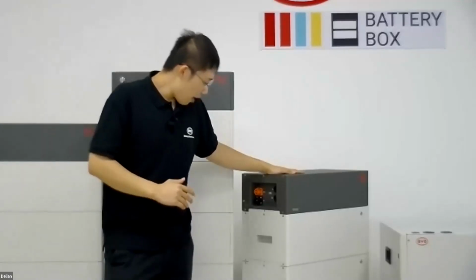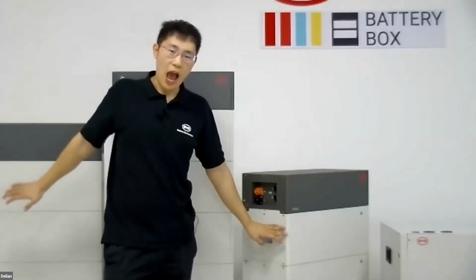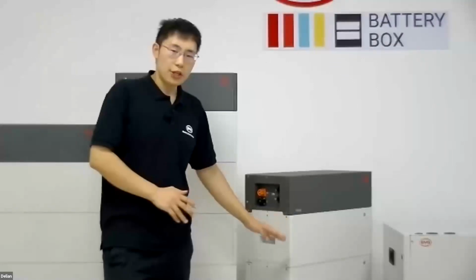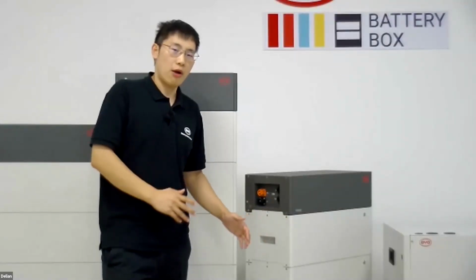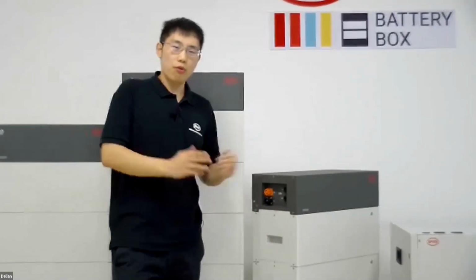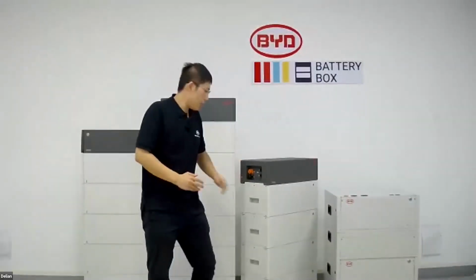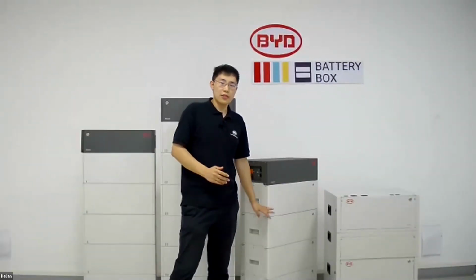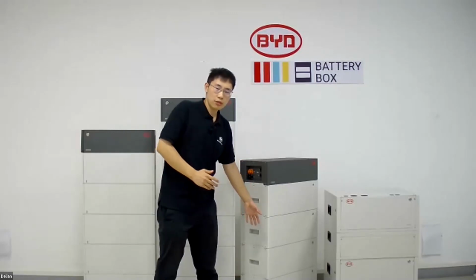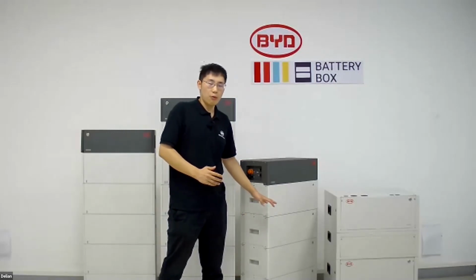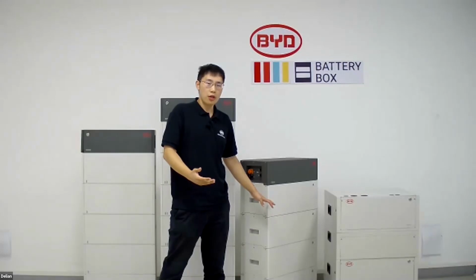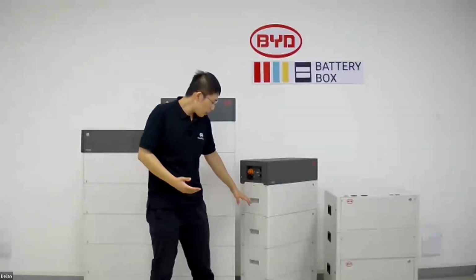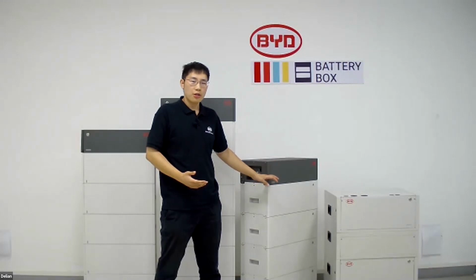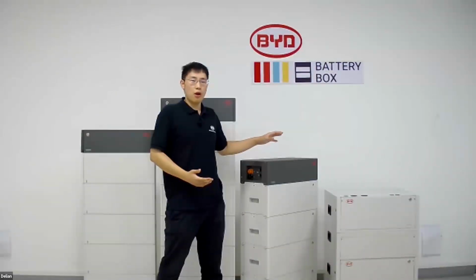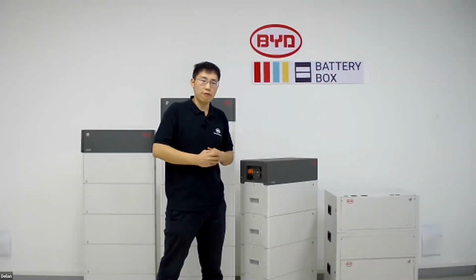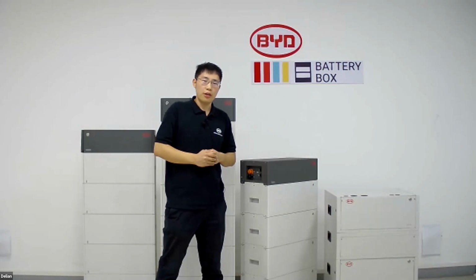For the LVS, unlike the high voltage, each module is connected in parallel, which means we don't really have a minimum number for the LVS. You can start from one module, which is 4 kWh. Then you can go for a single tower, up to 6 modules, giving you a capacity of 24 kWh.